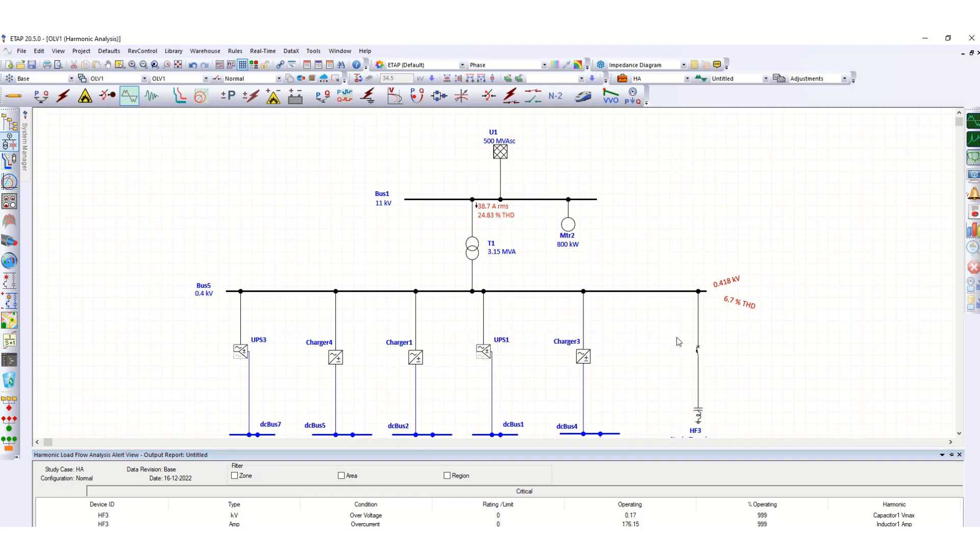Now you can see here 6.7 percent. Previously it was 7.36 percent, now it is 6.7 percent THD. And here, previously it was 27.06 percent, and now it is 24.83 percent THD.